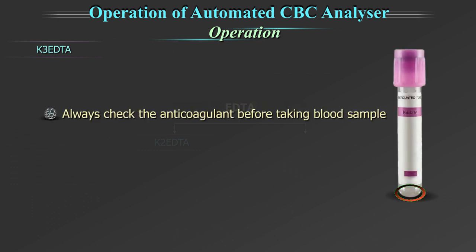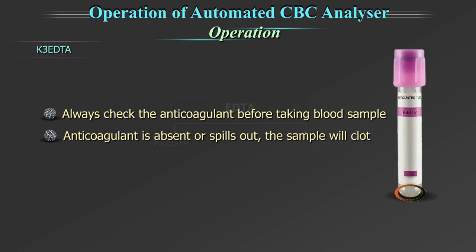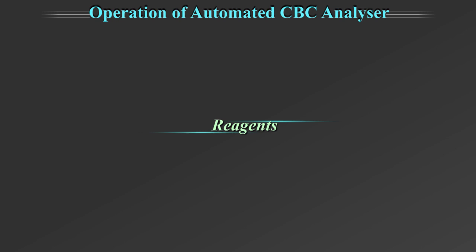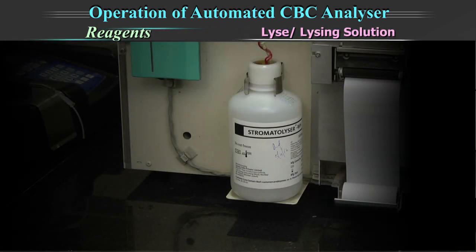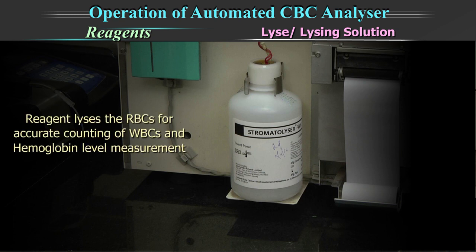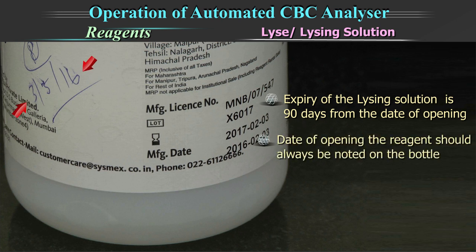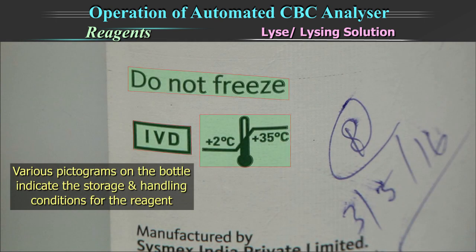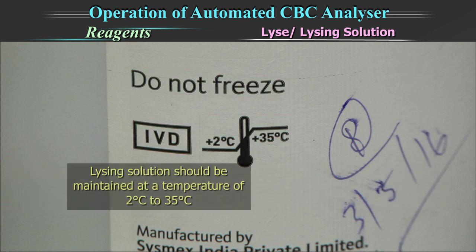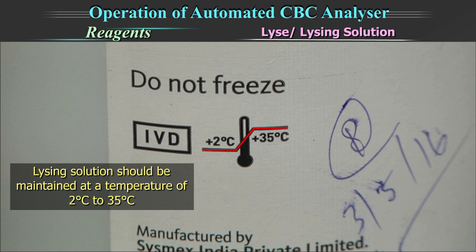Always check the anticoagulant in the K3 tubes before taking a blood sample. If the anticoagulant is absent or spills out, the sample will clot. The lysing solution — for example, Stromatolyser — lyses the RBCs for accurate counting of white blood cells and hemoglobin level measurements. The expiry of the lysing solution is 90 days from the day of opening. Please check the expiry of the reagent on the label or from your manufacturer. The date of opening should always be noted on the bottle. The lysing solution should be maintained at 2 to 35 degrees centigrade.